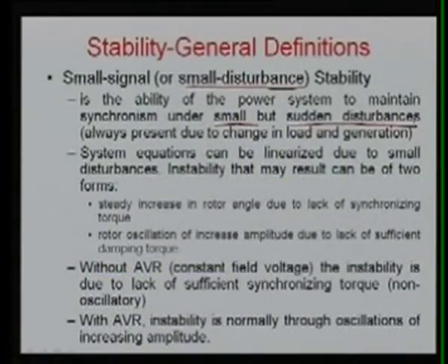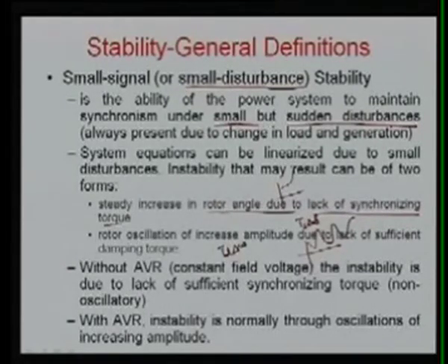Instability that may result can be of two forms. One is the steady increase in the rotor angle due to lack of synchronizing torque, that is your Ts delta delta, and another is rotor oscillation of increasing amplitude due to lack of sufficient damping torque, that is Td del omega. So it can be due to this region and it can be with this region. Here it is oscillating, and you can see it keeps on increasing with the oscillation and the system becomes unstable. Here your angle keeps on drifting, the change in delta is continuous, it is an aperiodic change, and that is due to the lack of synchronizing torque.